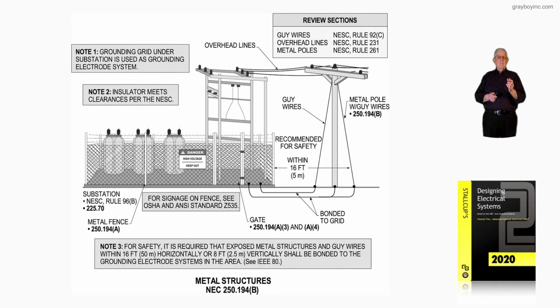Also, for outside usage, 225.70. The fence itself is 250.194A that we reviewed. Now, the recommended review sections for guy wires and how they would be grounded or isolated is National Electrical Safety Code Rule 92C, as in car. Overhead lines, National Electrical Safety Code Rule 231. Metal poles, National Electrical Safety Code Rule 261.